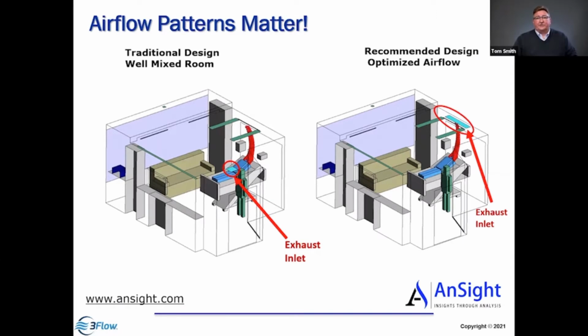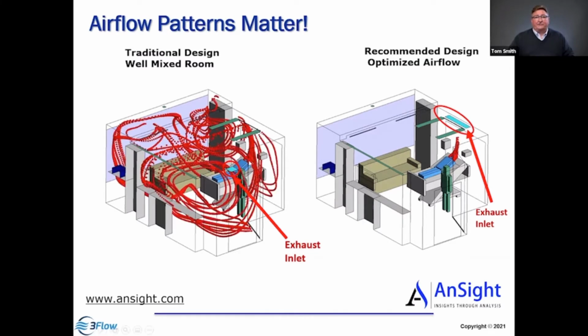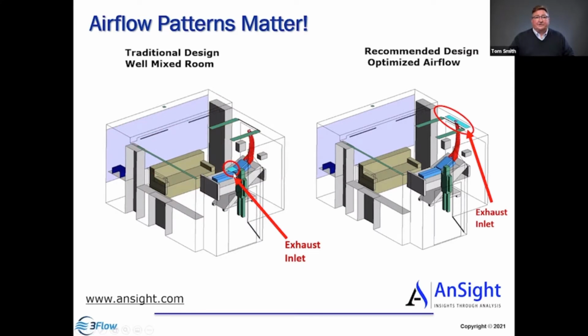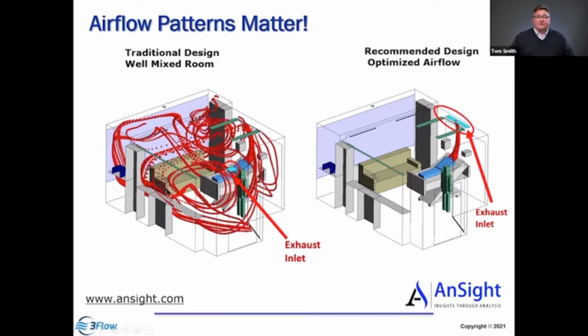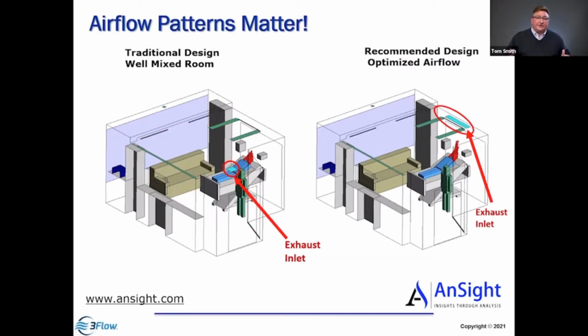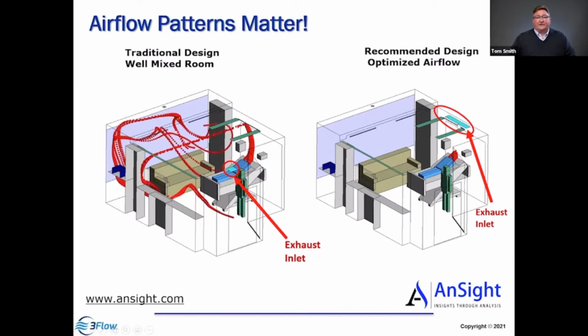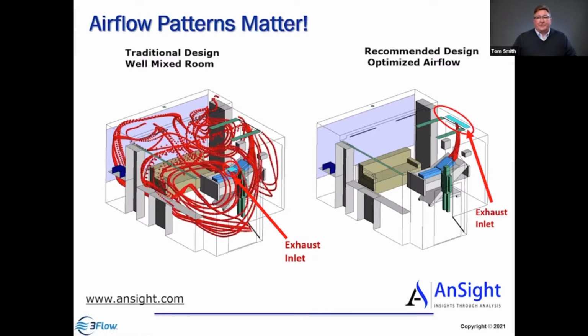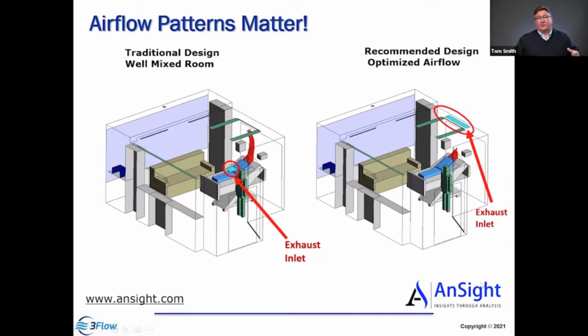We're using computational fluid dynamics to show the trajectory of particles that are exhaled from our infected person. And on the one on the left, because of the airflow moving away across the bed to this exhaust location versus the one on the right, we can see on the left that trajectory is taking those particles throughout the entire space, ensuring that everyone's exposed and every surface is contaminated. Now we look at the one on the right. Just by locating the exhaust in a different place, we now get a much more effective control of that effluent, and we're minimizing the risk to the occupants. So this is an important concept around ventilation effectiveness and why airflow patterns matter.